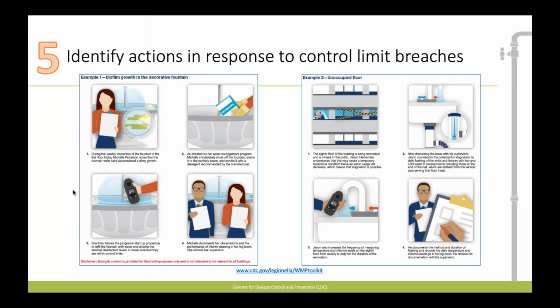That if, you know, at the 5th floor of your building, the temperature coming out of the hot water faucet just isn't quite hot enough, knowing that maybe you need to go back and change the temperature on your water heater, or maybe there is a balancing issue and something needs to be changed within the piping.